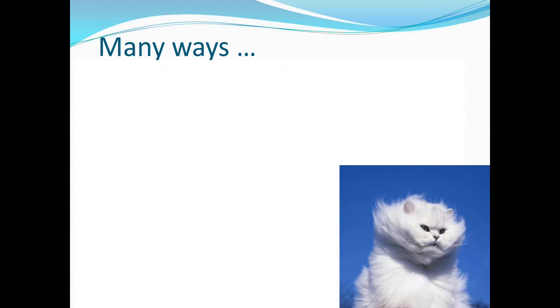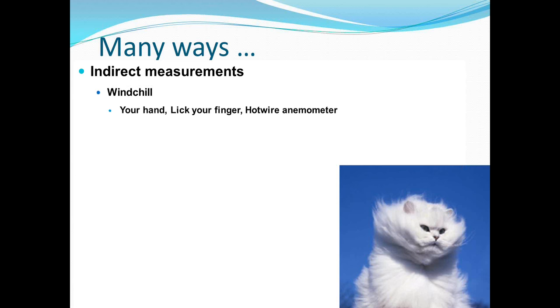There are many ways to measure airflow. Many we consider indirect measurements. Windchill-based methods — like a hot wire anemometer — measure the heat transfer away from a surface based on air velocity, which is density-dependent. The temperature rise method is used in furnace setups with a known heat input, only as accurate as the manufacturer's calibration. Static pressure drop uses pressure drop over a known restriction — usually a heat exchanger or A-coil — but that restriction can change if the coil is wet or dirty.